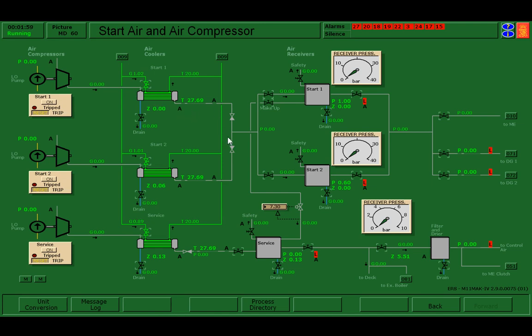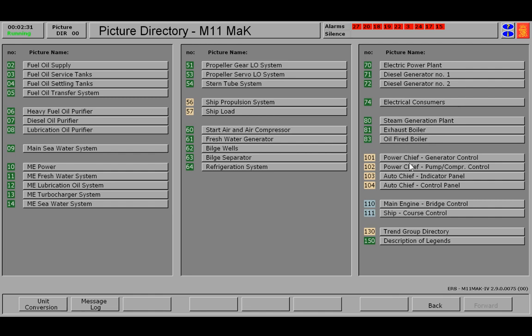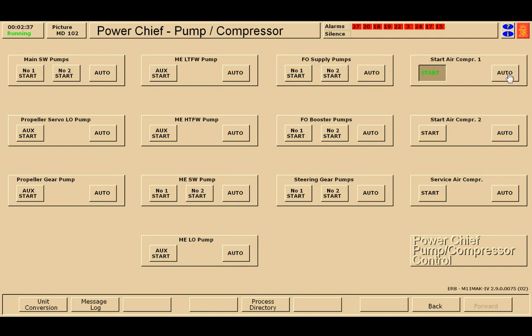Once I have that set up, I can create my pathway for air through to diesel generator 1, and I could turn on my start air compressor number 1. Start air compressor number 1 will eventually fill up my start air 1 tank. So at this point where I have cooling water and my pathways created, I would be okay to turn on my compressor control. So I'll turn them into auto.